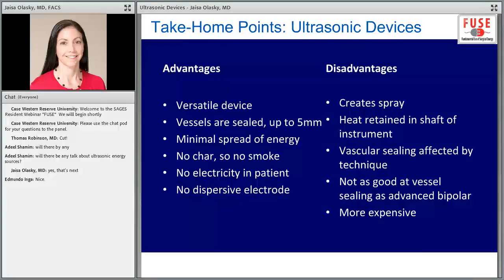So the overall take-home points with the ultrasonic devices, as I mentioned, it's very versatile. There's minimal spread of energy, no electricity going through the patient, which is really key for patients with pacemakers and other devices like that. And you don't need to worry about a dispersive electrode. You don't have to worry about where it's going to go or what metallic implants they might have. And then the disadvantages, again, it's expensive. It's probably not as good at vessel sealing as the advanced bipolar instruments are. And there's a lot of technique involved, both with the coaptive coagulation of vessels and also with how much tissue tension you use, what your blade excursion settings are, and those other factors in terms of cutting through the tissue.